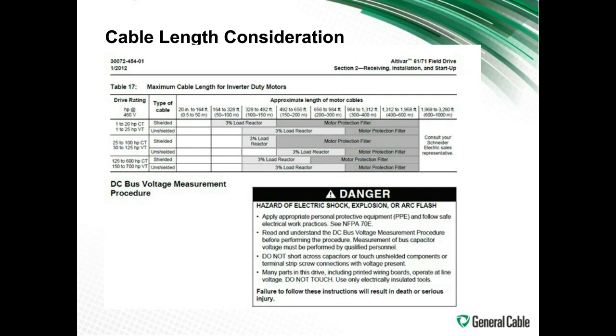So this is a slide that actually shows you, I've taken a page out of Schneider's guidebook on how long you can have your motor cable. So let's look at this. Let's say we have a 20 HP motor, and we need the drive away from the motor by like 500 feet. Let's take that as a possibility. Well, in order to do that, if you look at all the possibilities for this, you need to have some type of motor protection filter in order to get that distance.